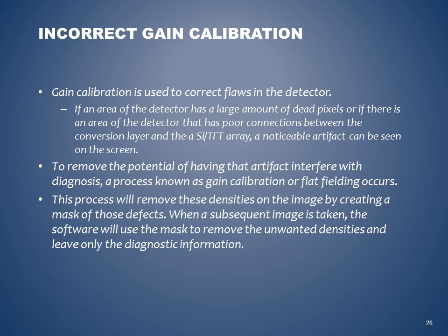If an area of the detector has a large amount of dead pixels, or if there is an area of the detector that has poor connections between the conversion layer and the a-Si TFT array, a noticeable artifact can be seen on the screen. To remove the potential of having that artifact interfere with diagnosis, a process known as gain calibration or flat fielding occurs. This process will remove these densities from the image by creating a mask of those defects. When a subsequent image is taken, the software will use the mask to remove the unwanted densities and leave only the diagnostic information.